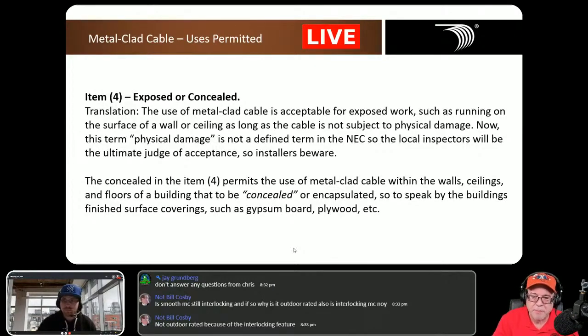However, just because it has to pass that without damaging the conductors in 10 full samples, that doesn't mean it's rated for physical damage locations. Like rigid, IMC, and EMT, which under 2020 code are now okay for physical damage locations, though they never were before. Schedule 80 PVC is okay for places subject to physical damage, but not MC. Even though MC is flexible and tends to move out of the way, it's still not rated for subject to physical damage.